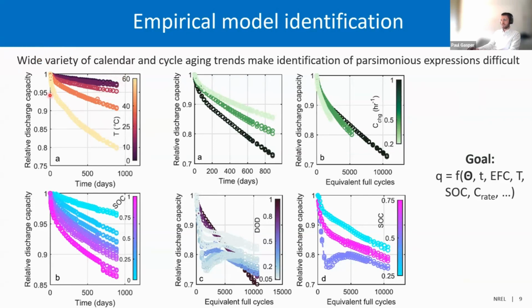For example, here we have calendar aging on the left, at different temperatures - loss of capacity over time due to storage temperature. It also varies with storage state of charge. Then you have cycling degradation, which is additional to that calendar fade, and that might be a function of your charging or discharging rates, average operating state of charge, or operating depth of discharge. So there's a wide variety of trends here.